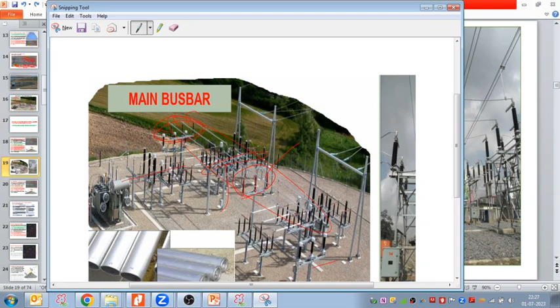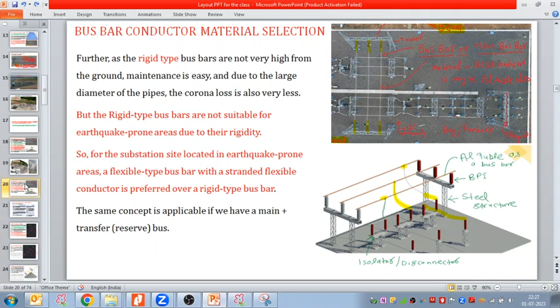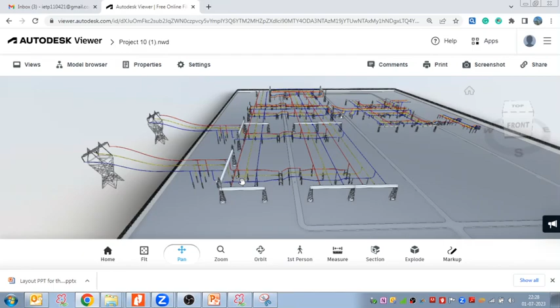After one bay usually we take the support, but when it comes to the flexible bus bar, after each bay the support would not be required because my installation height is higher than the tubular bus bar, and we are using conductors placed on the support structure, proper tower and beam. So in that case the support locations we can increase. When we use flexible bus bars, main and transfer or reserve, both bus bars are strung by insulators, called strain insulators, through the beams or gantries. So here I have the beam. This is my bus bar strung with the help of the insulator.